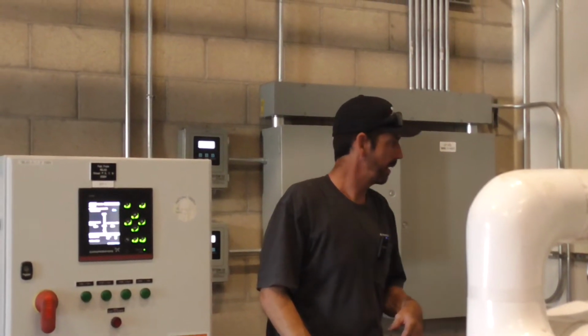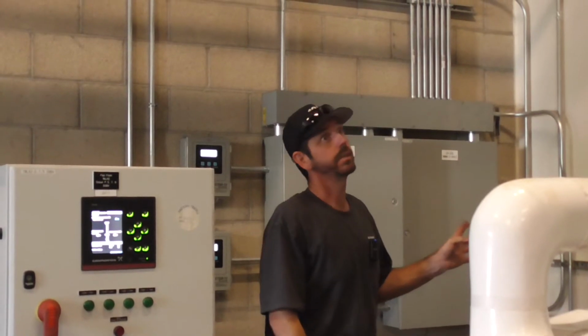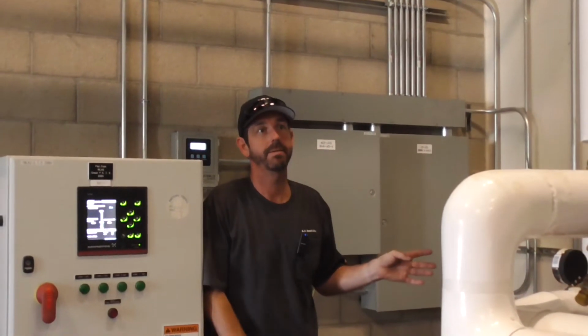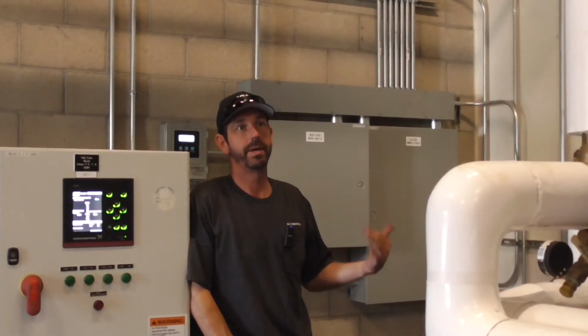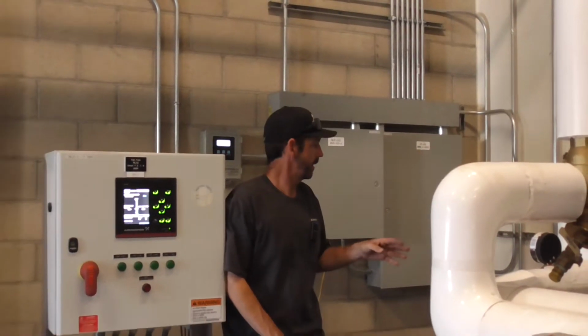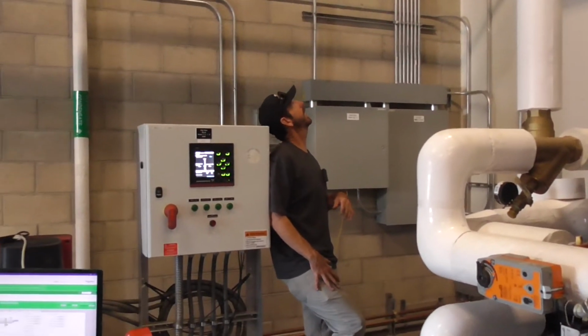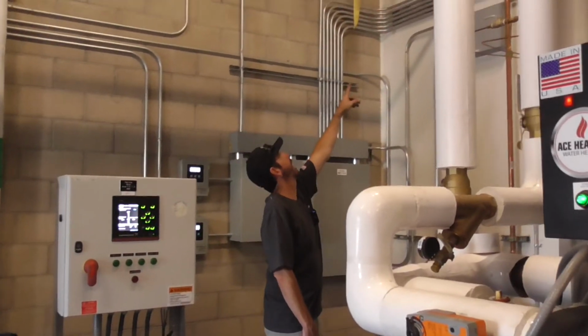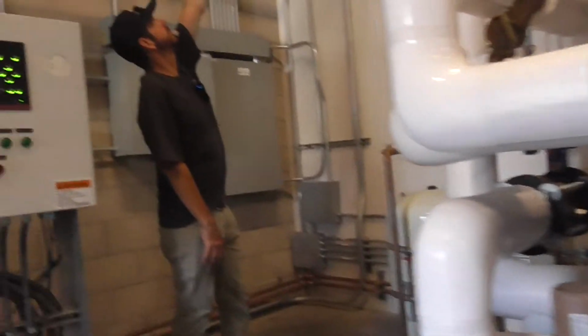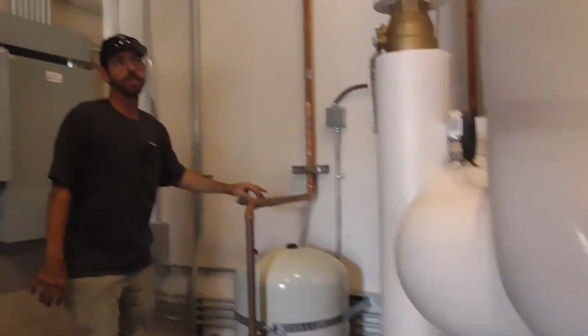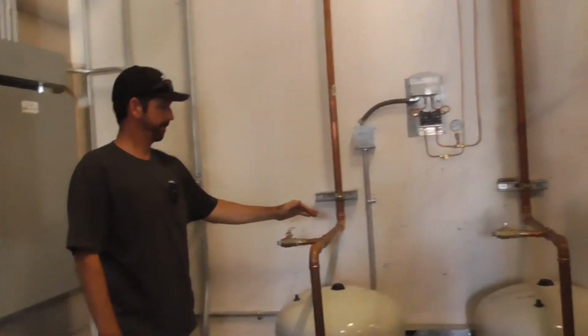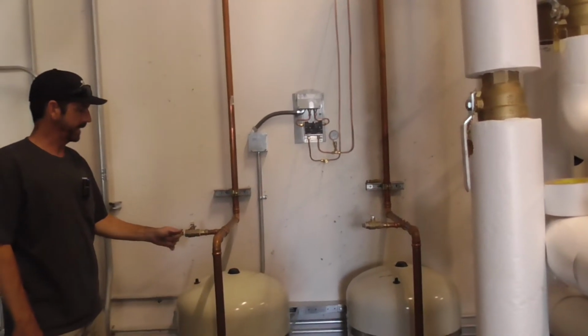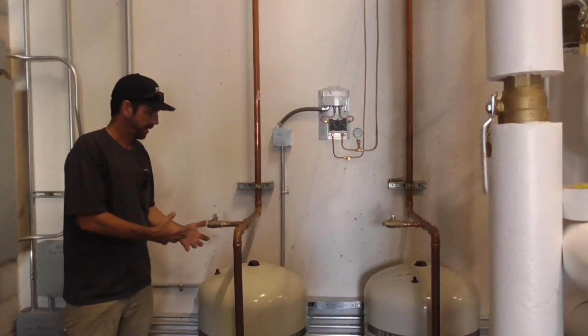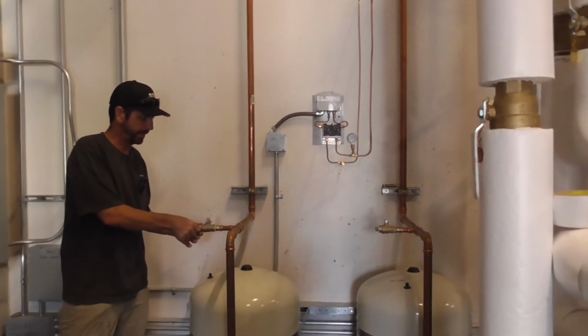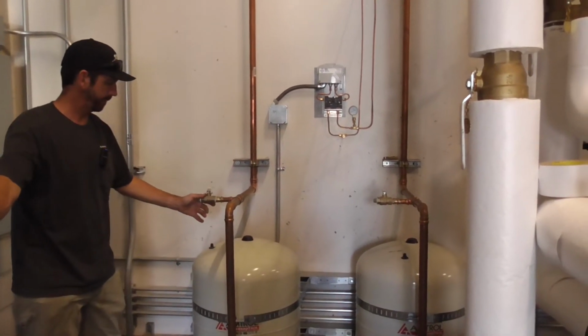Have you guys checked expansion tanks before? Do you know how to check them? No? Let me review it my way. So how do you check an expansion tank? We're going to want to shut off our shut-off valve up there. Okay, so we shut off our valve. We need to make sure we drain the pressure off the tank. So we could take this plug out right here. I would put a hose bib adapter on it and run it to a drain over here.